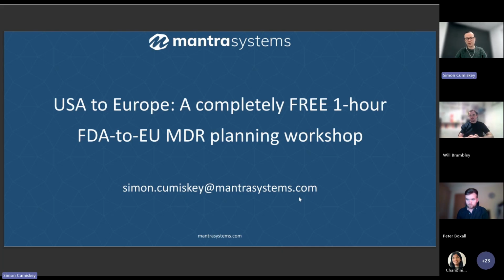There are some really common areas that we see that aren't done as well as part of that transition. The two main ones, I think, are the clinical evaluation, because it's new. Pete's talked about that quite a bit with the clinical evidence. But the other gap that we see a lot is in the risk management, where a very common approach to risk management in the US is an FMEA. And really what a notified body would expect is a slightly different approach to that risk management.